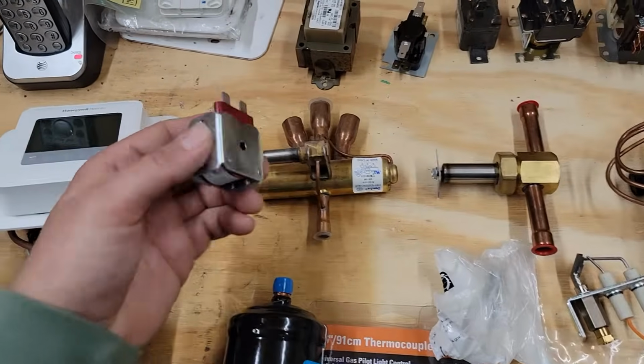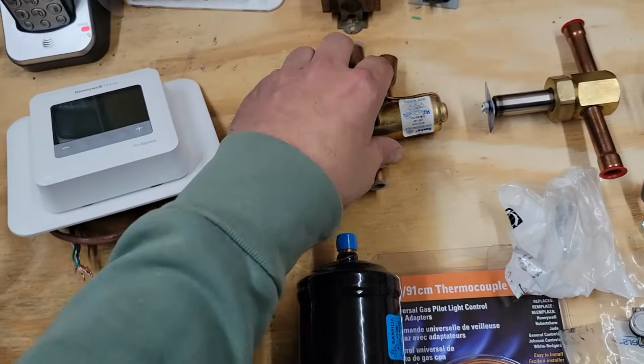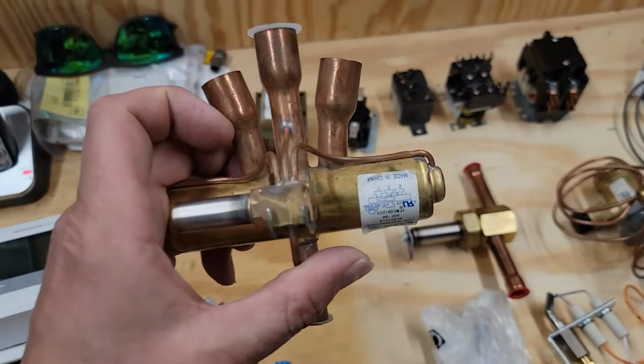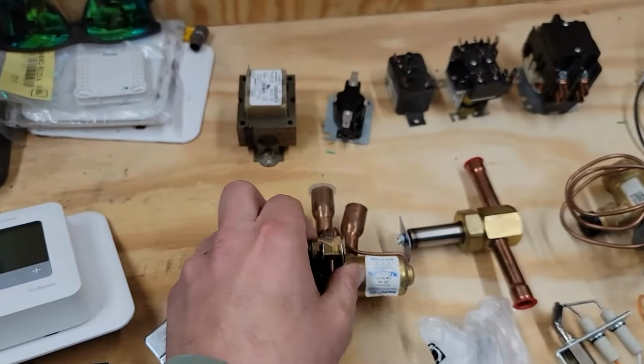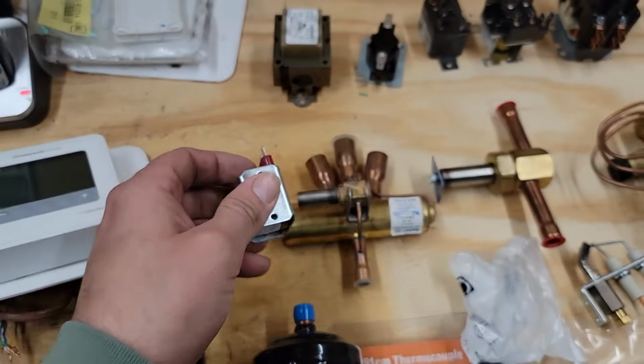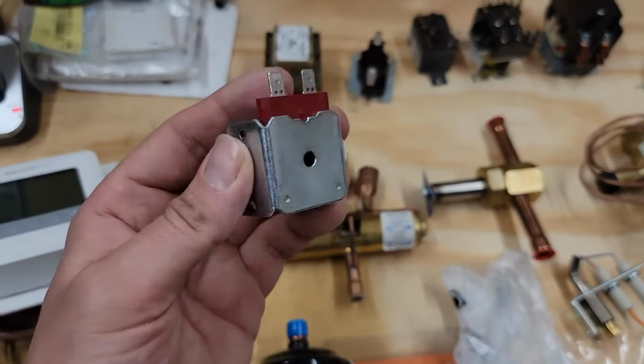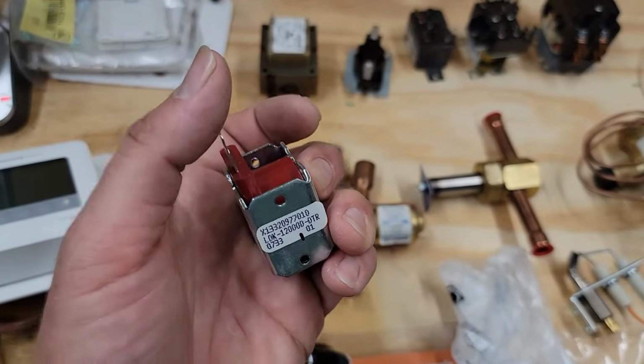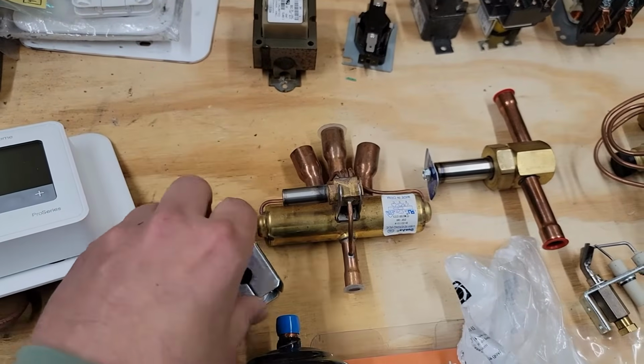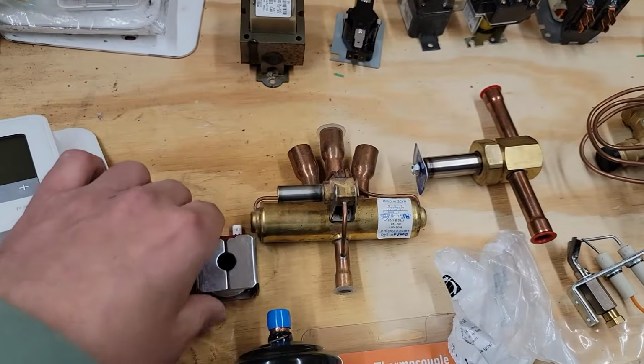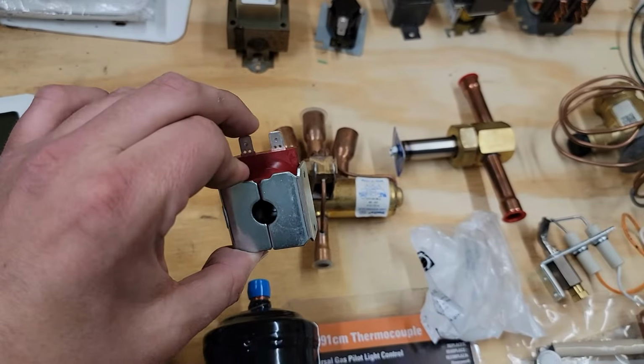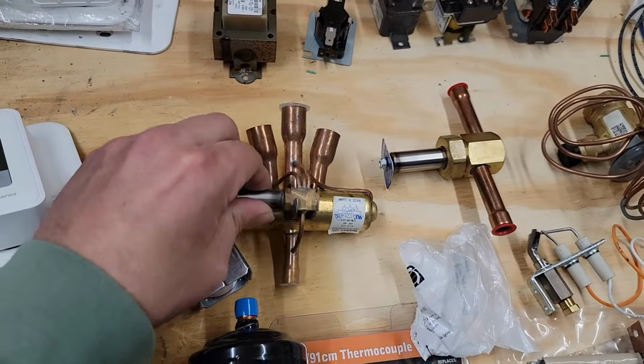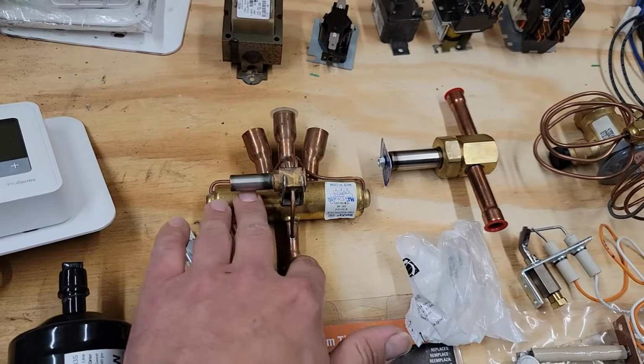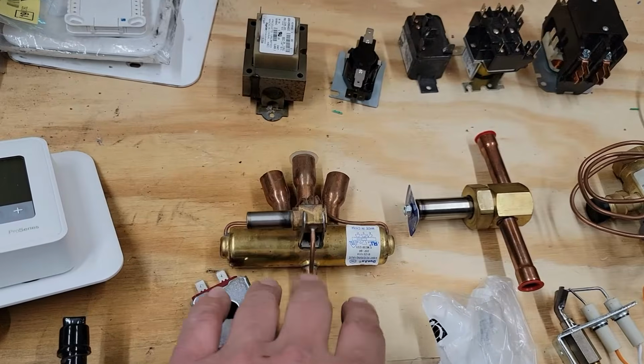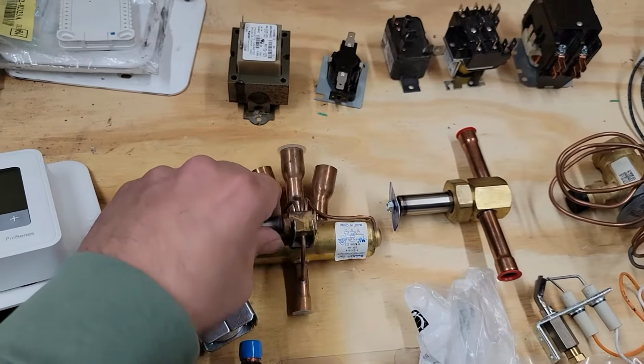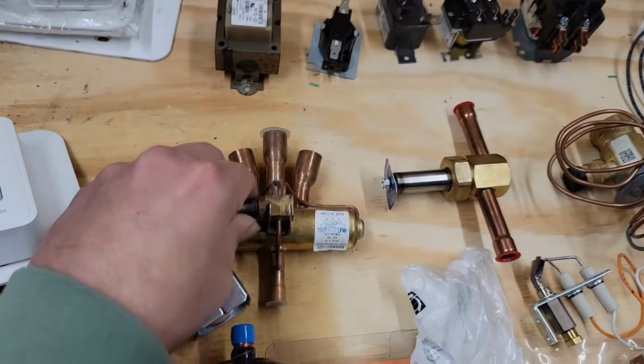So that brings me to the next part. This was filter dryer. This is a reversing valve, and the reversing valve switches the flow of the refrigerant in the system, and it uses this coil to energize. So this coil, usually you have 24 volt coils, but I've seen coils that are 240 volt. So this right here would slide on to that, and then once the power is inputted or energized right here to this coil, then that would activate this valve. And usually, different manufacturers have energizing either in heating or in cooling, and you would be using O or B for energizing the reversing valve.